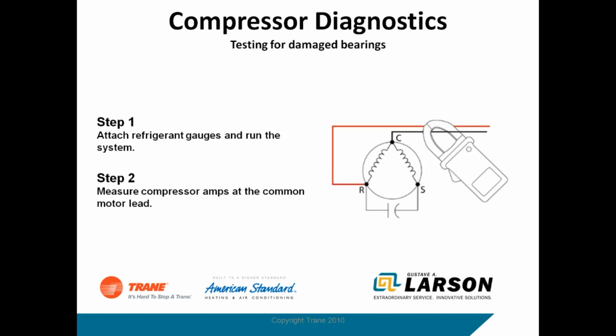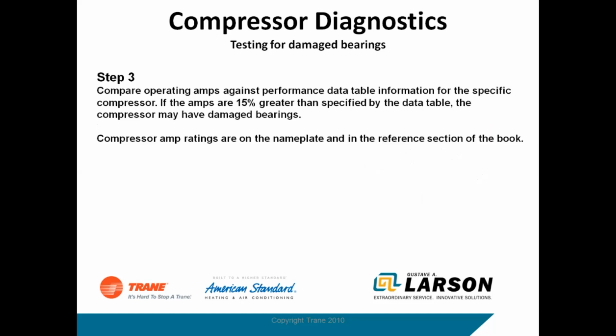Testing for damaged bearings. Well, there's a couple of things that can happen. If you've got a compressor that's running hot, again, verify we've got the proper charge. And if we have the proper charge, then let's take some amp readings and see where we're at. If it's a three-phase compressor, you should get equal amperage on all three legs. If you're looking at a single-phase compressor, make sure we take an amp reading on the common wire. We can do the run and the start separately if you want to, but the common wire is going to be our true amperage. And if we've got an amp draw that's 15% greater than the data, we may have a problem with bearings in that compressor. It's going to run hot.